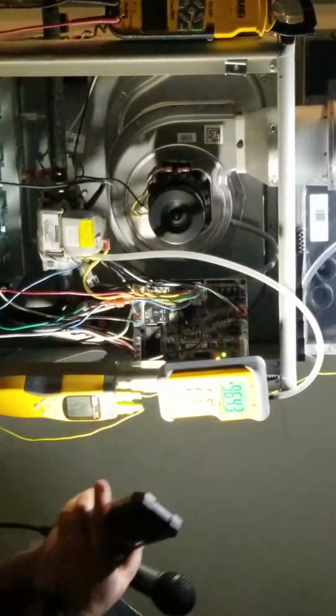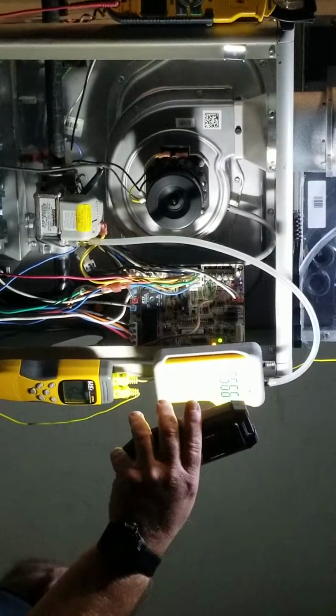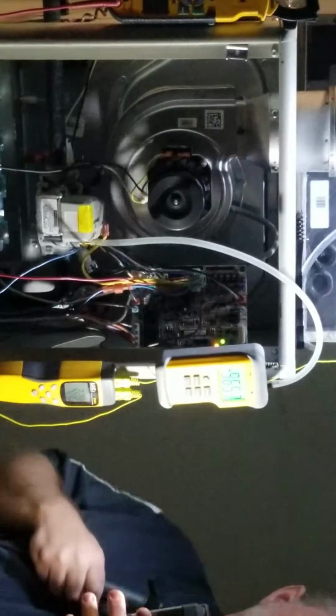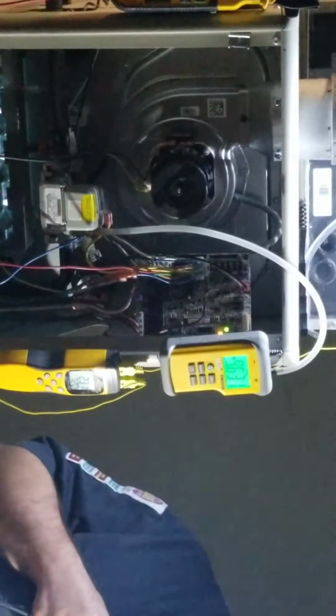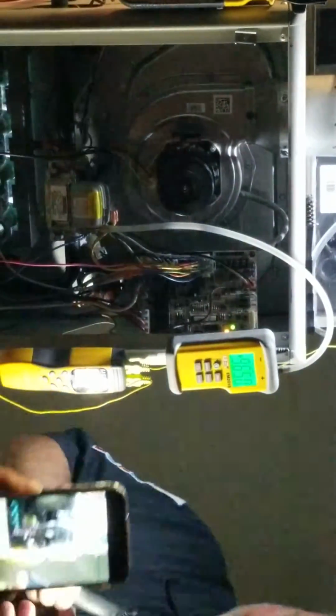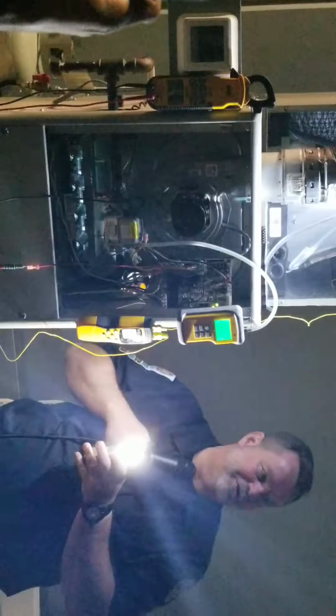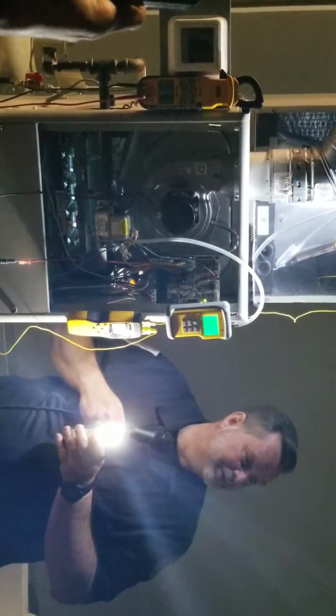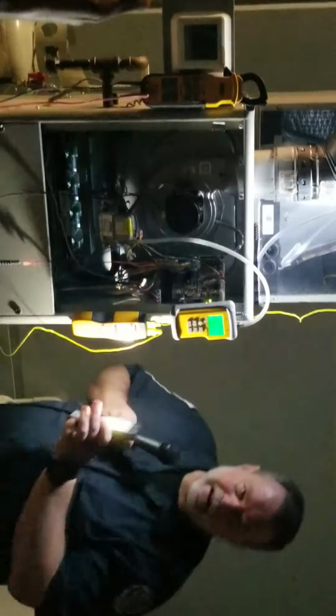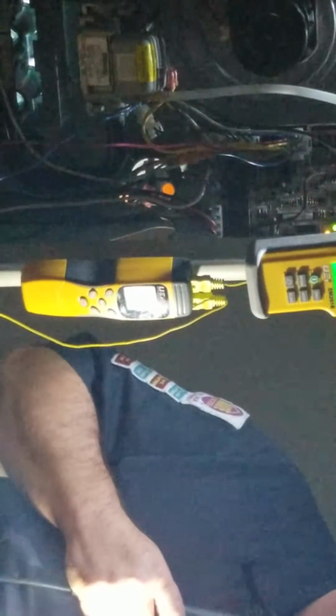No unplugging wires. I can literally push that switch right there and change that fan switch from high, medium low, and low, just like that. And when I do that, my temperature starts dropping in my heat exchanger. Remember we had a discussion about how much air we want moving over our heat exchanger? Guess what? We start moving a lot more cold air. Our rise on our heat exchanger goes down because we're moving more air. Does that make sense?